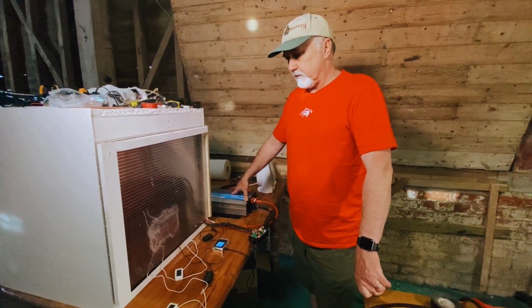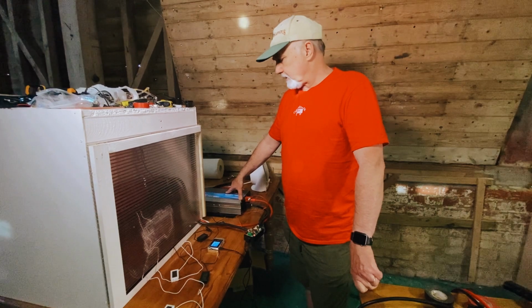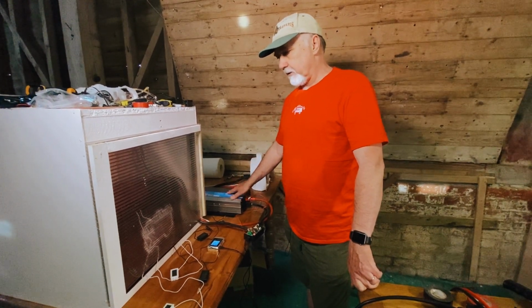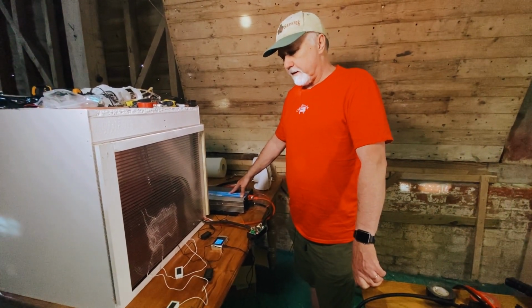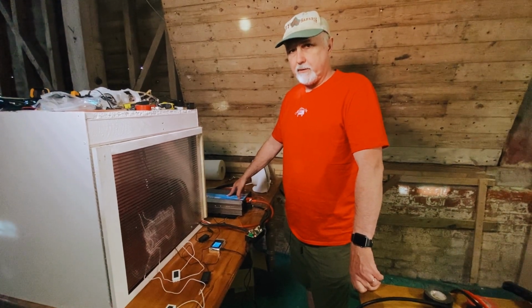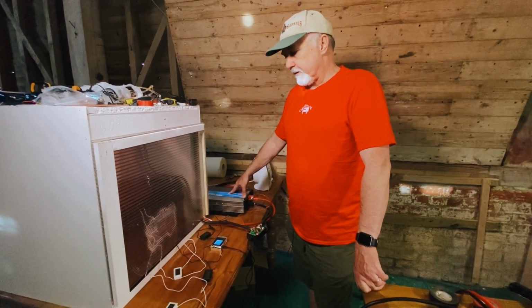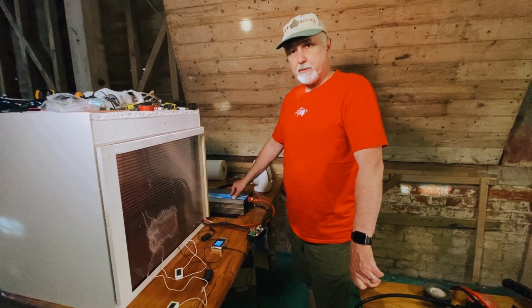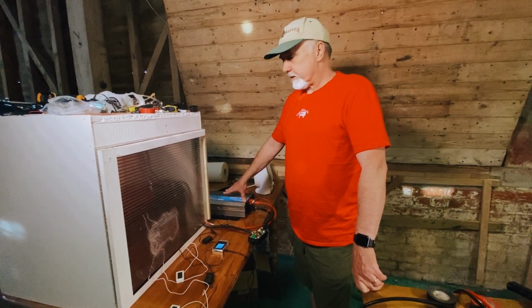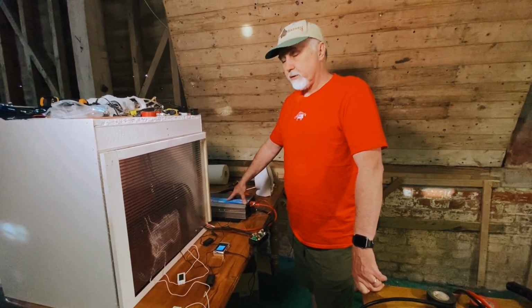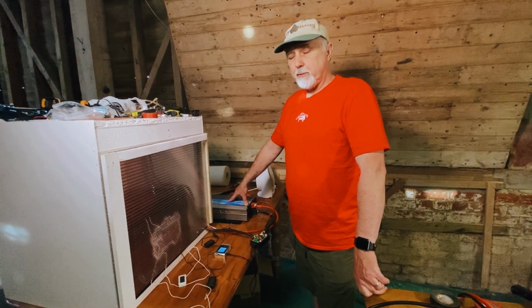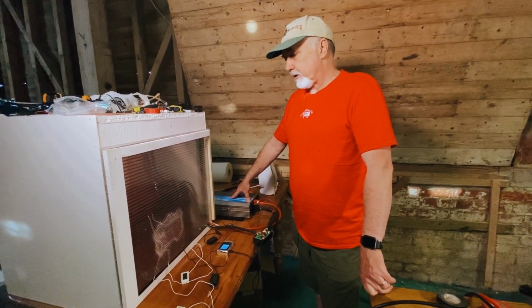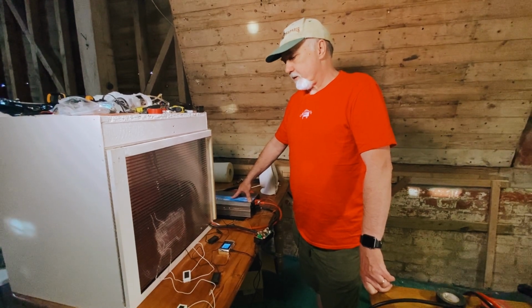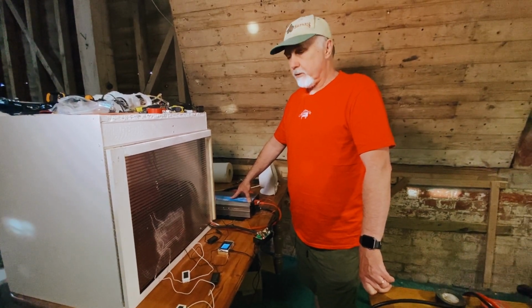We know that running an hour at such a heavy load on this particular battery yields a roughly 30 degree centigrade increase in temperature, which is quite acceptable because we're still around about 60 degrees centigrade, and we could go quite a bit higher. But we think that for most uses this battery is quite okay.